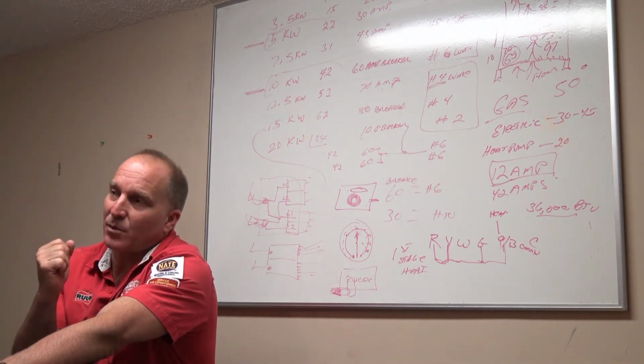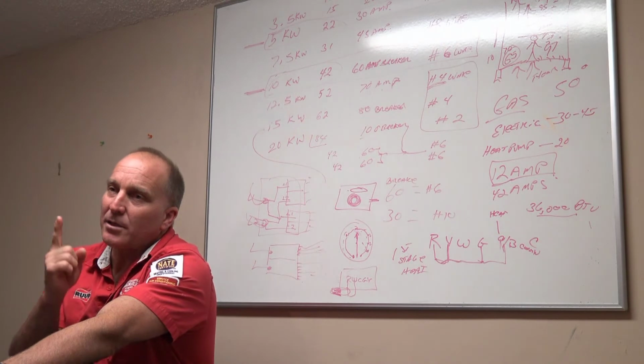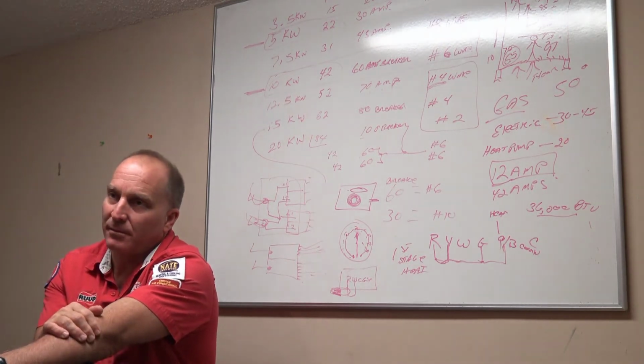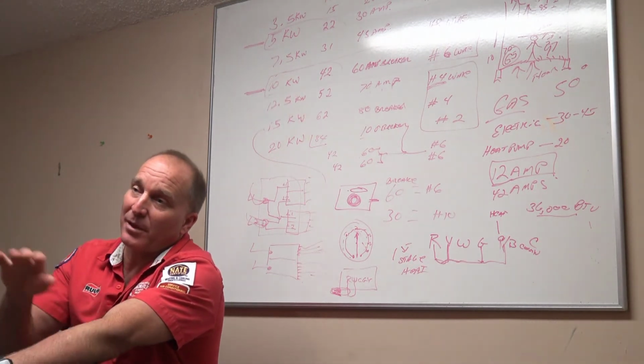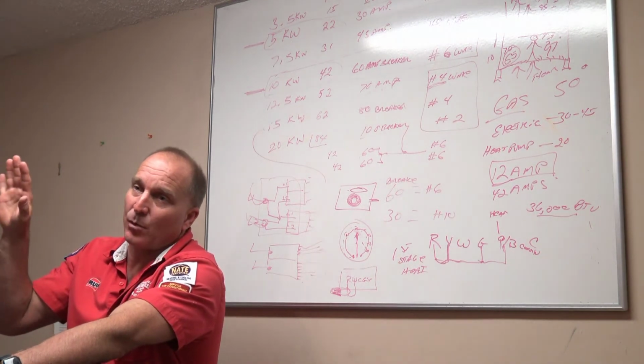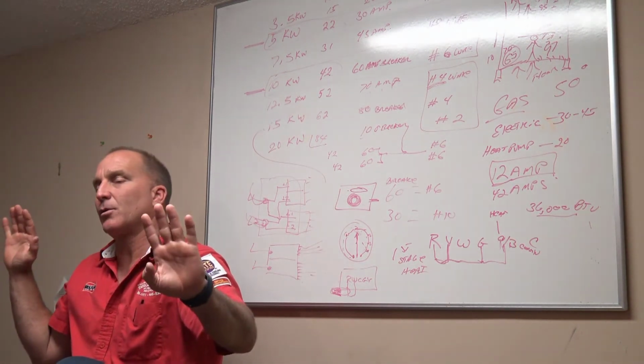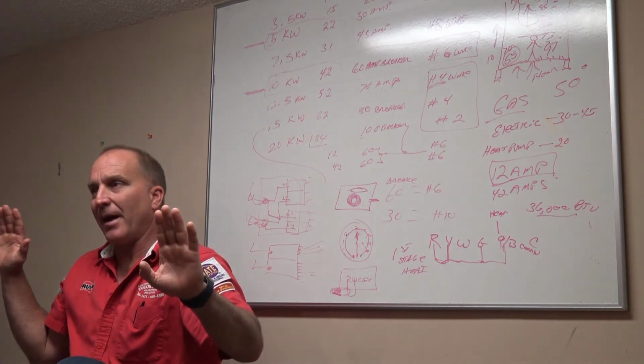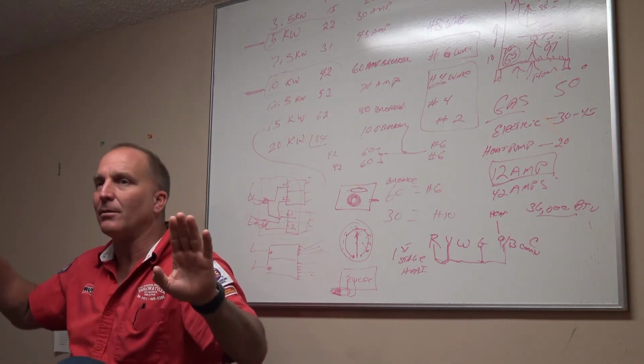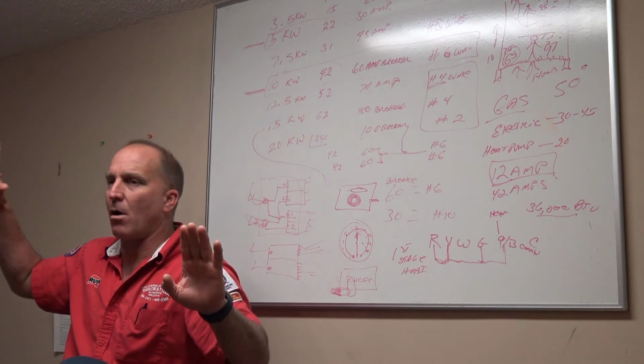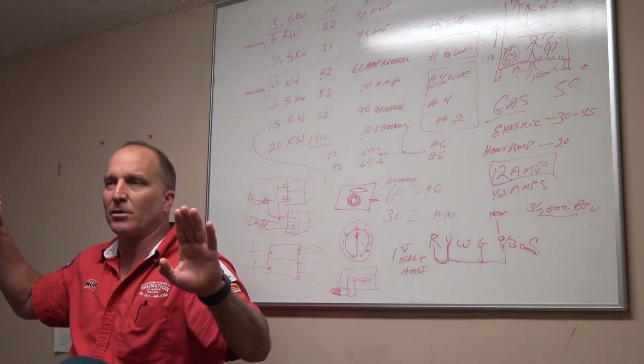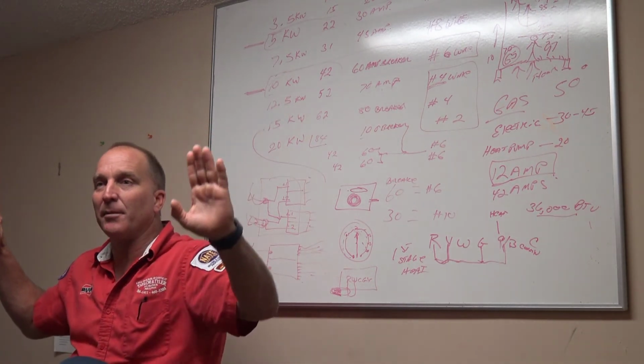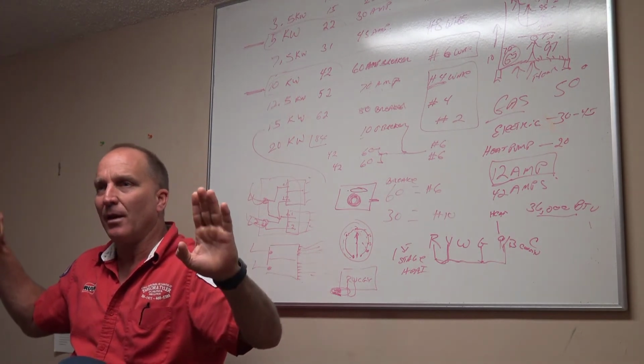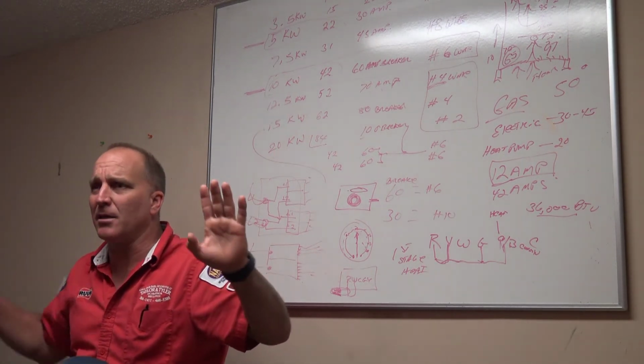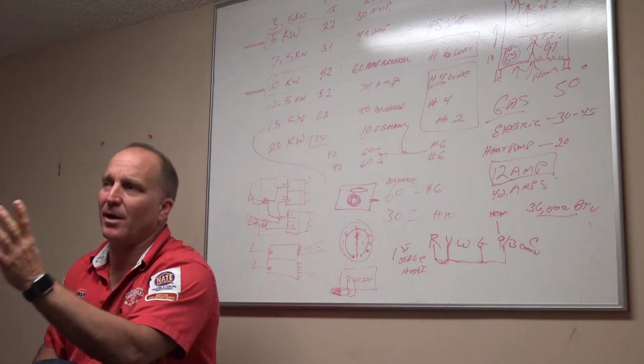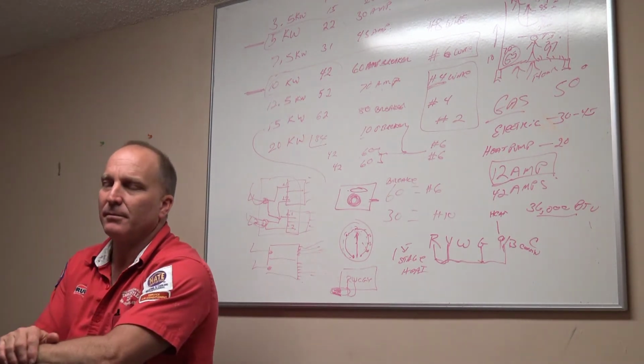Because a lot of times with electricity, the weakest point burns first. I have taken and replaced disconnect boxes in the attic that were burned up but never went to the main electrical panel. Next day, guess what's a strong connection now? Everything I just put in, right? It's all strong, it's all solid. Guess what burns tomorrow? Breaker. The breaker in the main panel, because it's now the weak connection. And I call up and they go, "You caused that because it wasn't like that yesterday." And I go, "No, I didn't cause it. I just didn't check it."